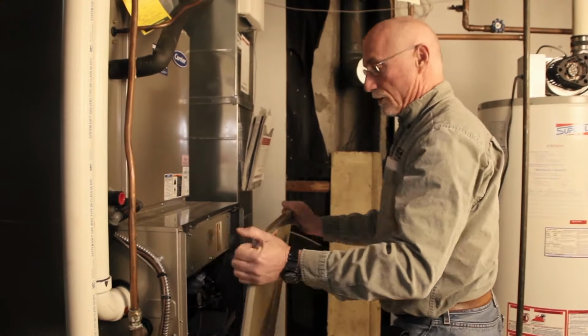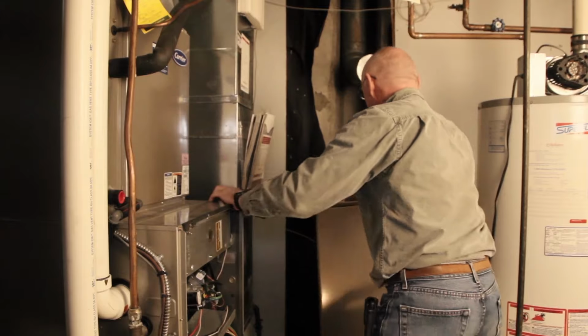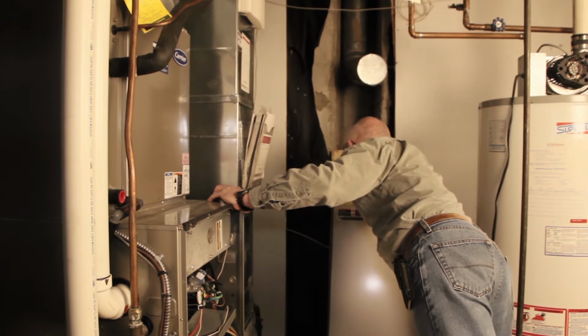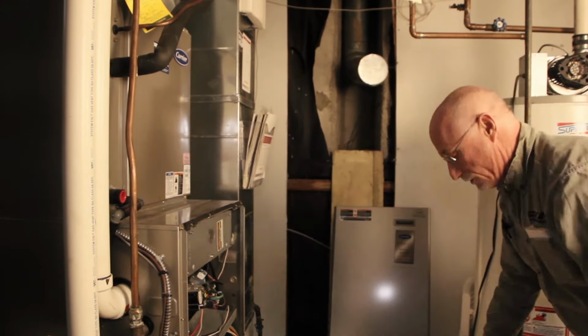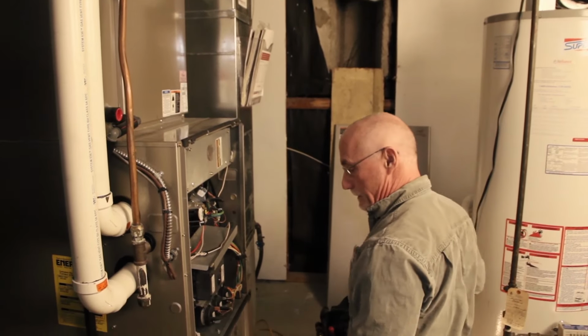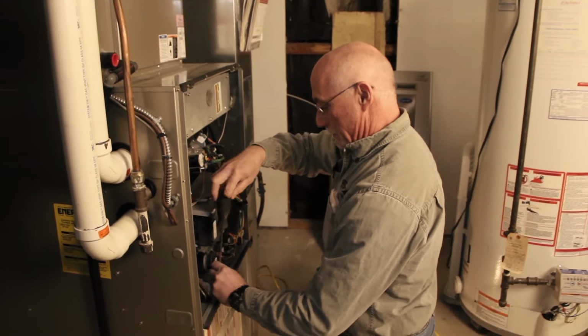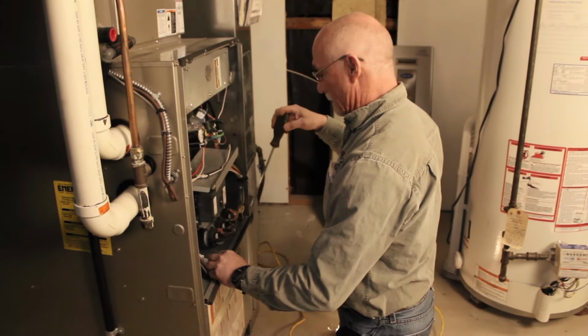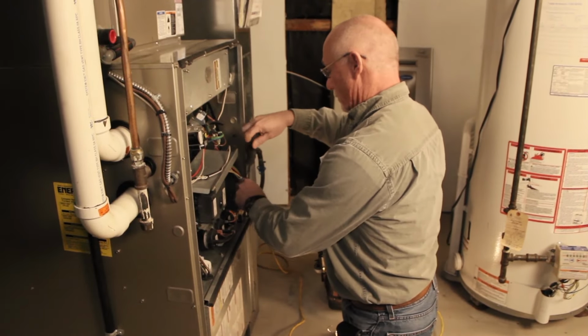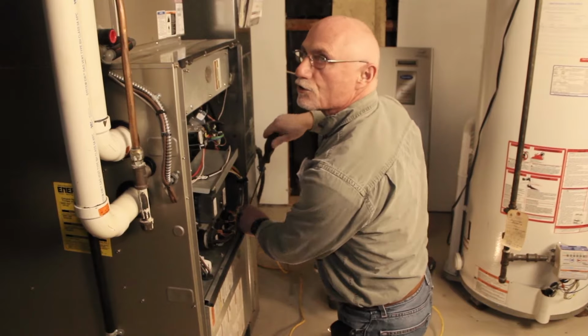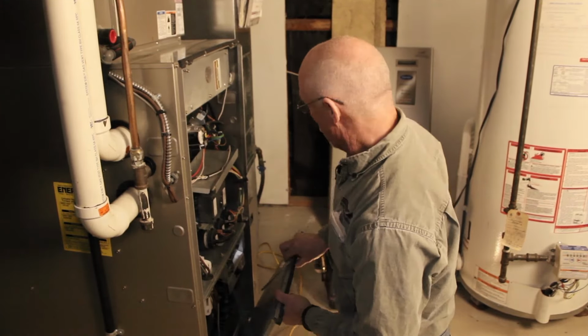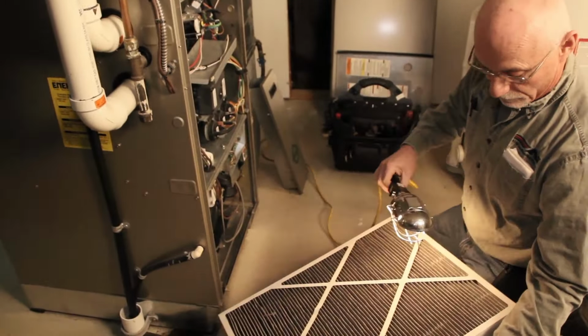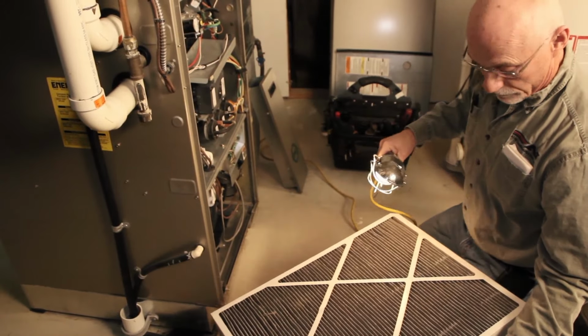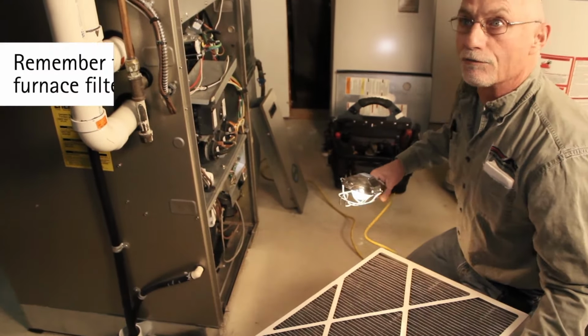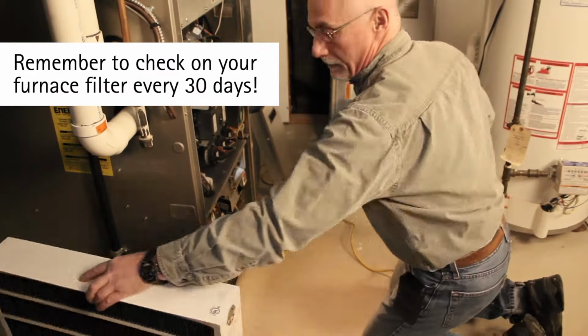Yeah, so what I'm going to do is I'm just going to take the doors off and we're going to do a little bit of a visual inspection here just to see how things look to begin with. This is going to give me the access to look inside the blower to make sure it's not all full of dirt and dust and all that stuff. So what I'm doing is just inspecting the filter to make sure that it's still adequate and it's not going to restrict any of the airflow and have the furnace overheat on you. And that does look fine.